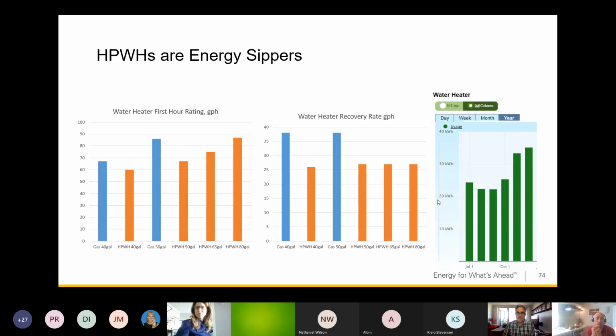Fantastic. Jane brings up tankless. Tankless somehow has sunk into our consciousness as efficient. But gas tankless use gas, and so they're not nearly as efficient in terms of greenhouse gas emissions as a heat pump water heater. And if you're comparing electric tankless, as people tend to do, they think, well, electric's better, let me do electric tankless. Comparing that to a heat pump water heater, there's no comparison. An electric tankless will use 3x as much kilowatt hours as a heat pump water heater. So the electrification, decarbonization trend needs to be heat pump water heaters.